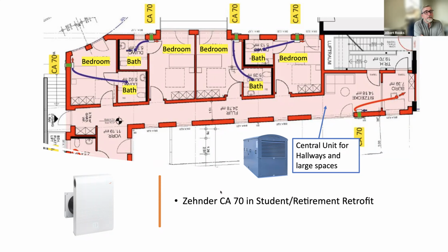So above that, on the right-hand side, we've got one that's right next to a bathroom, and it looks like they're running ducting. You could theoretically almost not run ducting, or run the ducting on the supply side and send it into the bedroom and just have the thing pick up exhaust in the bathroom. Their next one over, same thing, picking up exhaust in the bath, giving supply to that bedroom right there, even though it's pushed up against the wall. Another one over to the right, ducted to the bath, supplying to the bedroom. So essentially, this is a whole lot simpler and a whole lot more achievable to retrofit into a building because we only have to run one duct. In buildings like these, there's another way: if this building already had bath fans, you could leave the bath fans, so that could cover your bath exhaust.